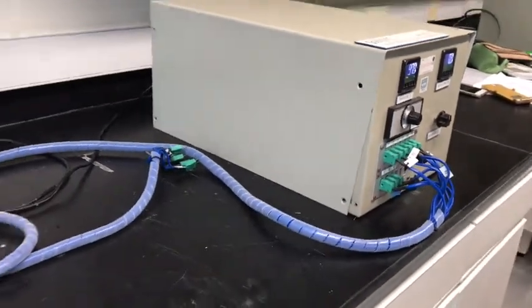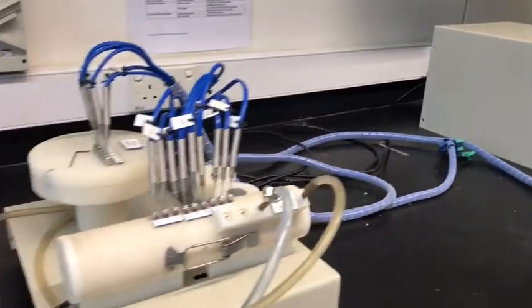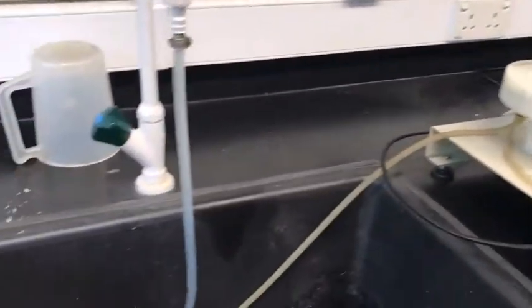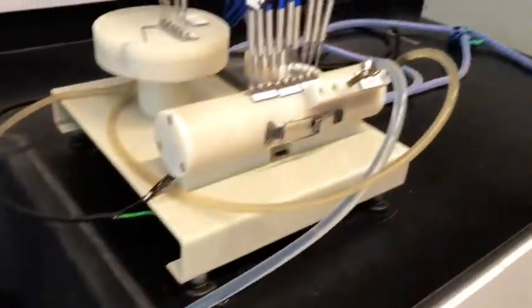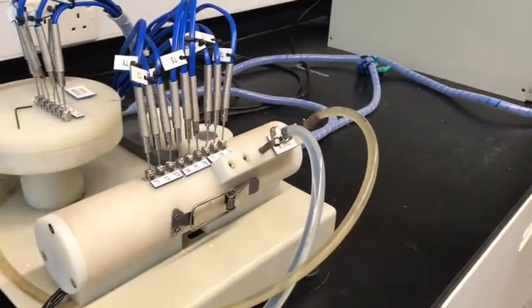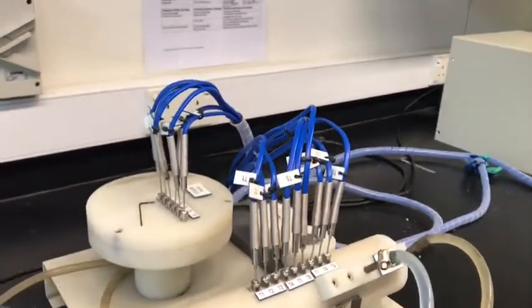Then we turn on the water supply and ensure that the water is flowing from the free end of the water pipe to drain. This should be checked here. Number 4, make sure the heater wire is connected to the back section of the control panel.